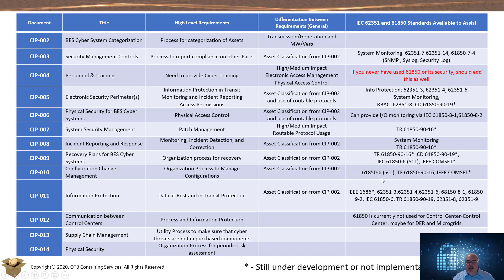Configuration change management — 61850's system configuration language is a major player in that. The ability to remotely update and patch, which is 90-16 and IEEE Comset, can all provide assistance there. Information protection is about data in transit and data at rest. IEEE has a standard under revision called 1686 that talks about various aspects that need to be implemented in an IED. There is a whole suite of 62351 and 61850 standards that provide assistance in securing and preventing threats for data in transit and data at rest.